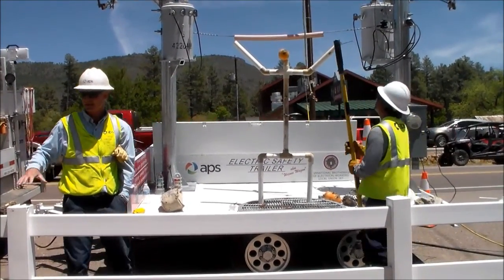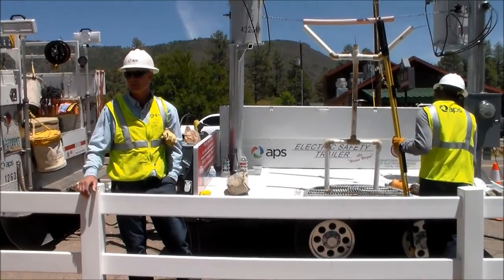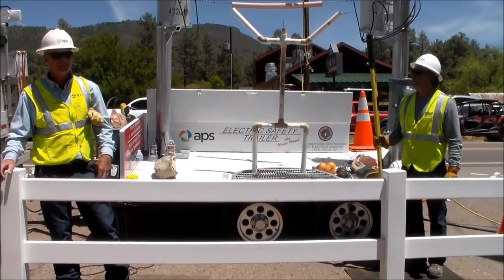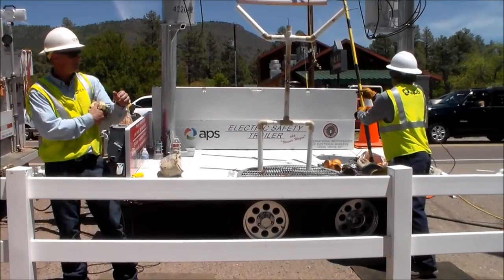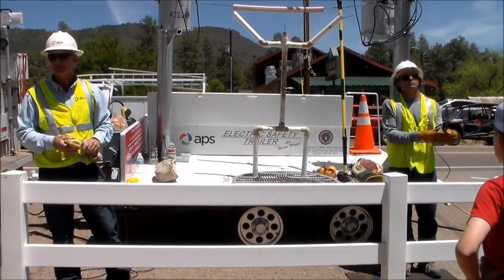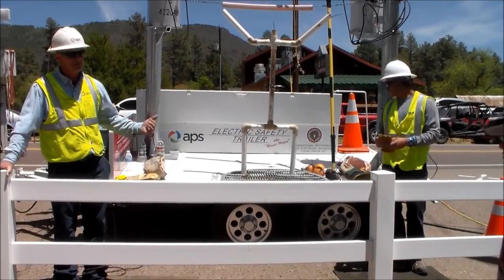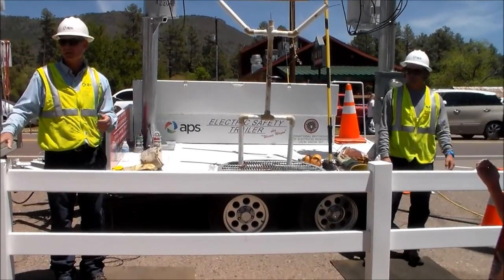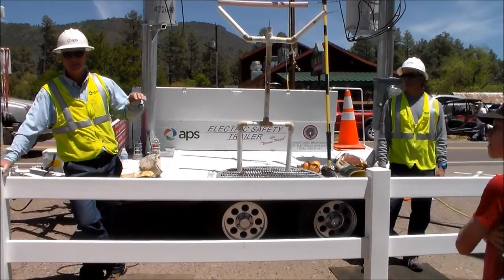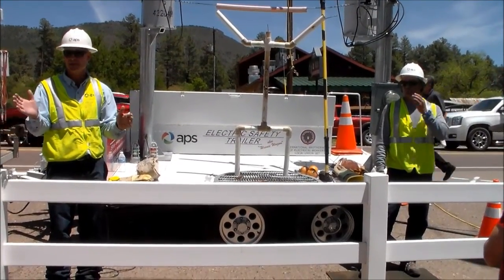We're here to talk about Firewise. APS has put into place a whole lot of Firewise programs. One of the things we do involves smart switches. The power line from the substation runs through the woods and all through the forest. APS doesn't want to start a forest fire. A tree could fall into the line and start a forest fire. We've installed what we call reclosers, or smart switches — a switch that opens the electricity and de-energizes the line.